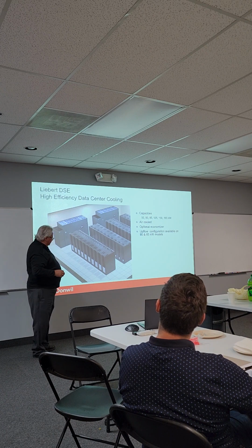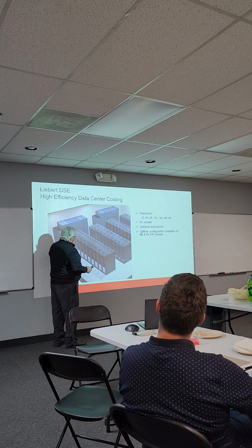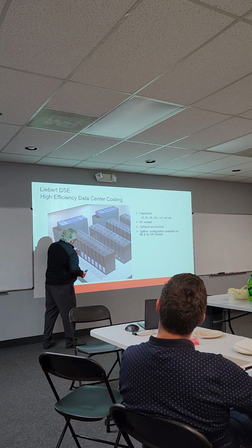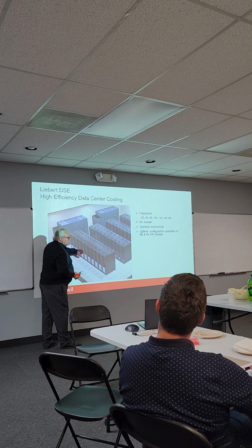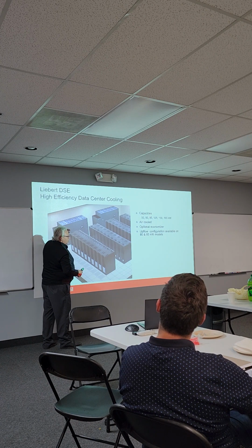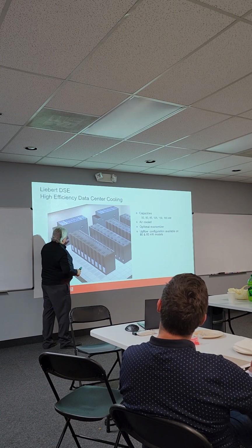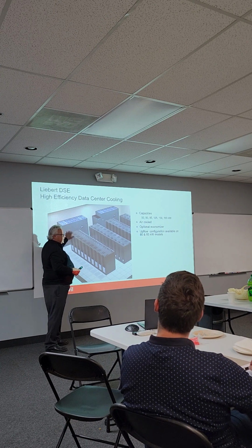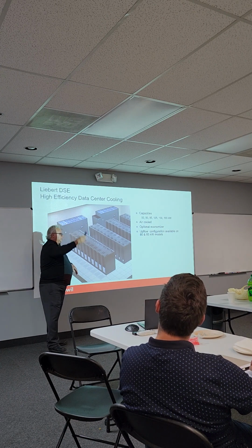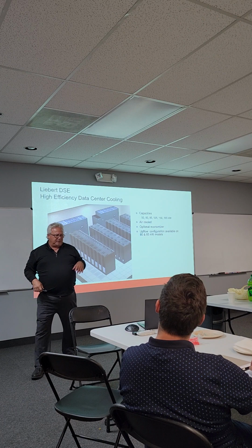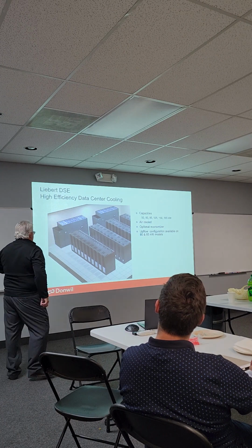Anybody? Sure. Yeah. So instead, this has a little quarter horsepower fan in it, these little servers. This thing's got a 20 horse motor. What's gonna win? This is gonna win. It's gonna pull the cold air along with the hot air. So we got this mix, and if the sensor's sitting right here, what's gonna happen? This unit's gonna say, I'm satisfied, I'm gonna shut the cooling off, and it's gonna short cycle and all this stuff. So just kind of remember the layout.